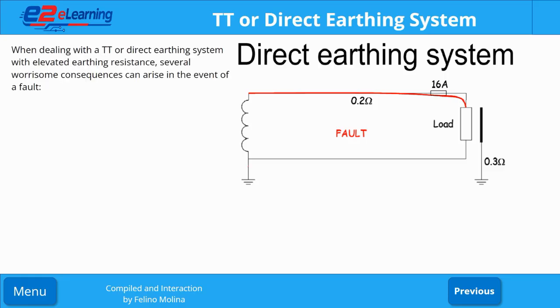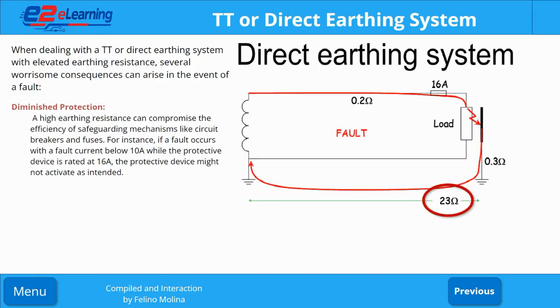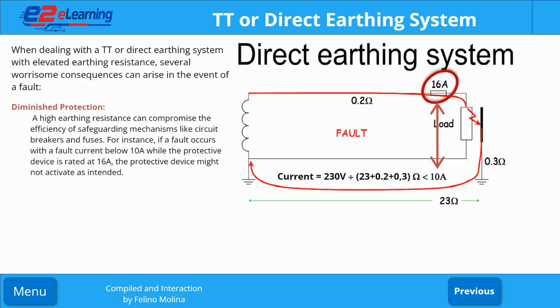When dealing with a TT or direct earthing system with elevated earthing resistance, several worrisome consequences can arise in the event of a fault. A high earthing resistance can compromise the efficiency of safeguarding mechanisms like circuit breakers and fuses. For instance, if a fault occurs with a fault current below 10 amps while the protective device is rated at 16 amps, the protective device might not activate as intended.